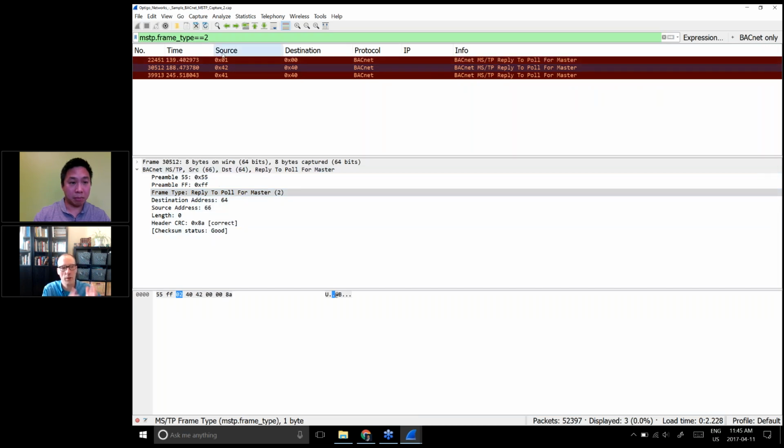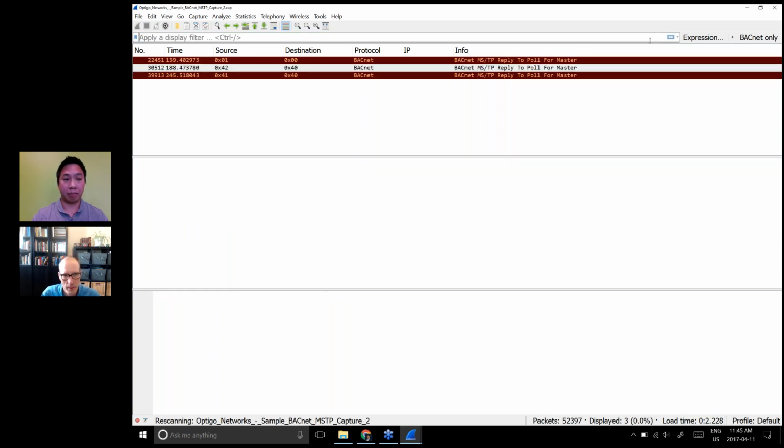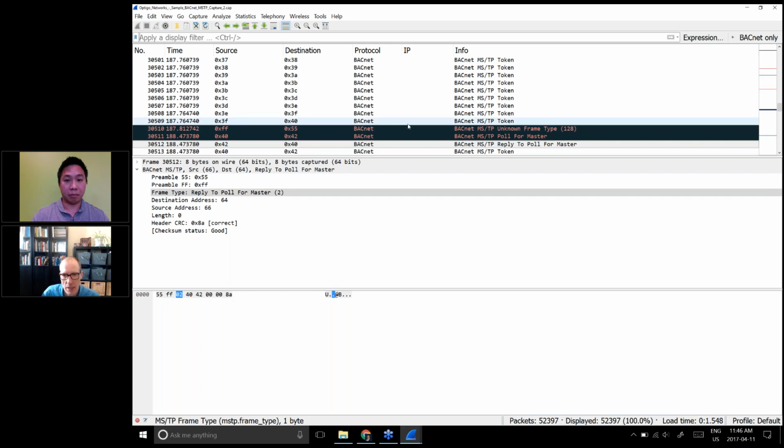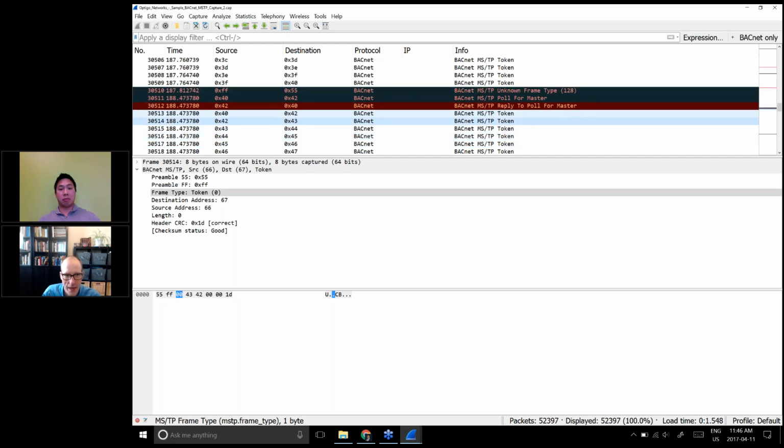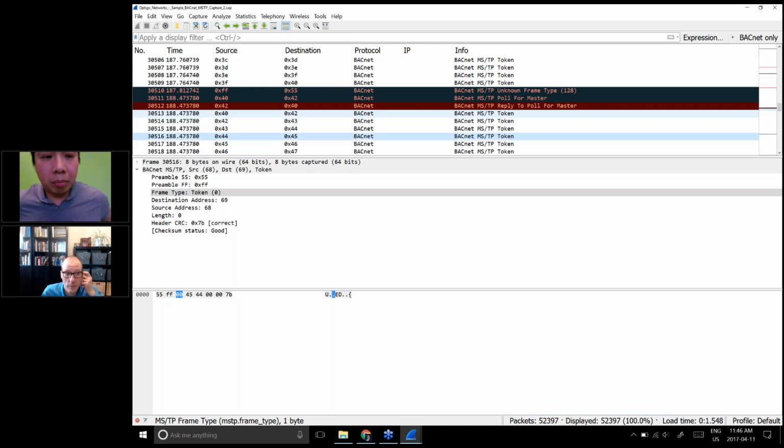So when you have a failure of the checksum and reply to poll for master, you've got an MSTP network that's hurting. If a CRC check is bad, it means more than likely there are wiring problems in terms of quality on the network. Stuff like it's not terminated properly, there are too many devices, the wire's too long, the wire isn't the right type, it's unshielded. All those sorts of issues on MSTP would lead to this kind of a problem occurring. But we can see how the network does run stably for a period and then falters. So it's very unlikely that this problem is caused by a bad device, like one device gone bad, because even here, if we check the reply to poll for masters, I don't think it's the same device each time it comes up. In any event, the CRC check basically cinches it as it's not likely to be a single device causing the problem. We're talking about electrical issues, not logical. Yeah, much harder to find.